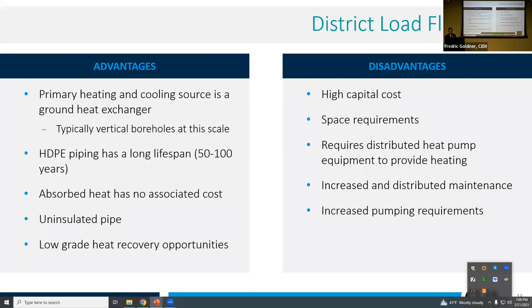Space requirements: you need to be near a body of water, own some land, have the real estate—or else find another way to utilize the transfer of energy using this low ambient, low-grade fluid loop. It requires distributed heat pump equipment to provide heating, and increases distributed maintenance. Maintenance is generally low on the loop itself, but it can get costly dealing with the actual equipment—this is refrigeration equipment, these are heat pumps, so the local HVAC technician needs to be a refrigeration tech. And as mentioned earlier, there are increased pumping requirements.